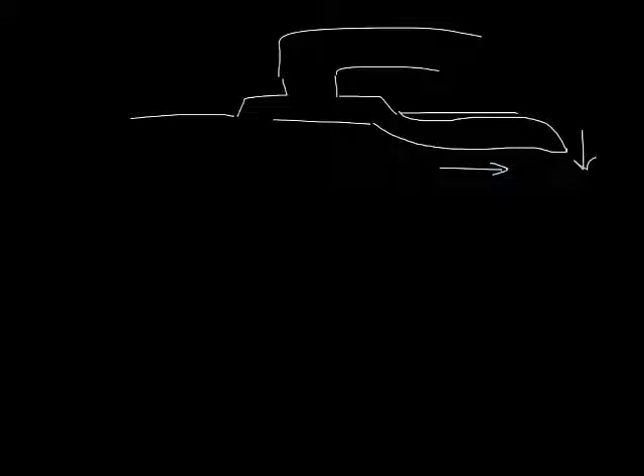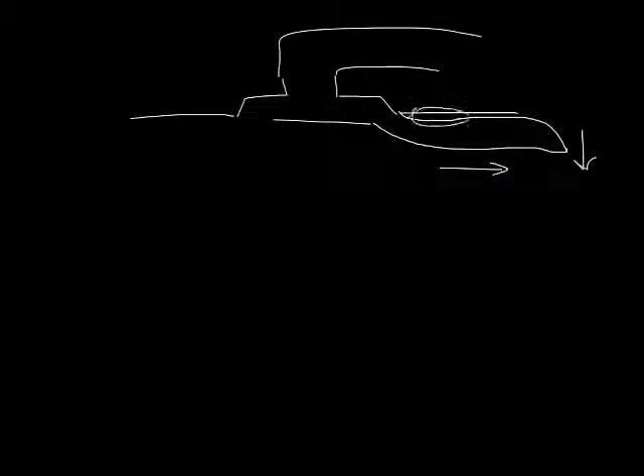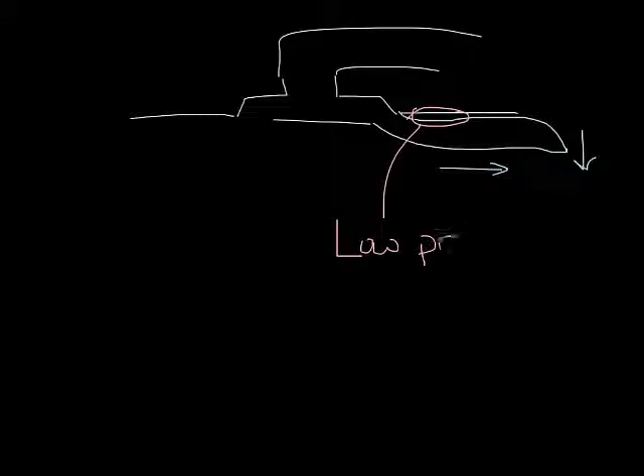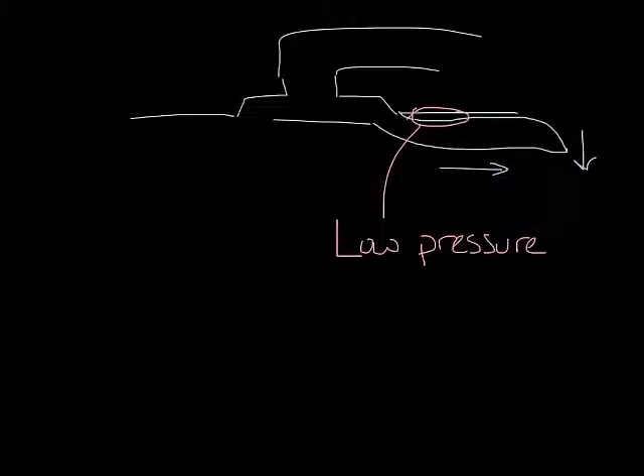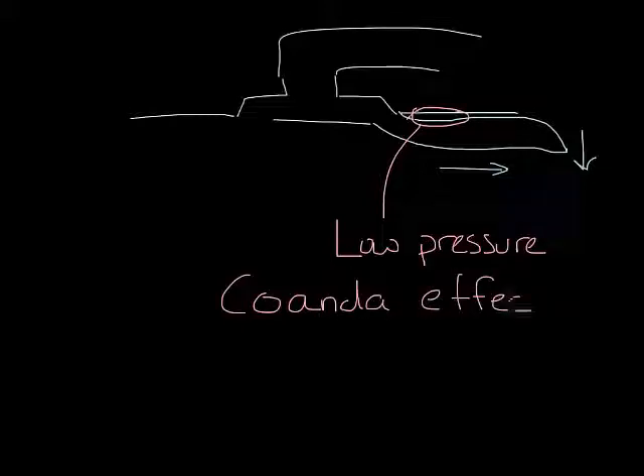In the throw podcast, I didn't discuss what makes the airflow across the ceiling in the first place, so let's look at that now. As the air leaves the diffuser, it creates a low pressure zone right here at the edge of the diffuser where the diffuser meets the ceiling. This low pressure zone creates an effect called the Coanda effect. This essentially makes the airflow stick to the ceiling and increases the throw of the diffuser along the ceiling.